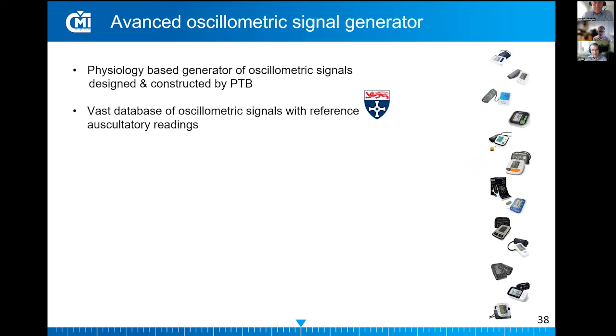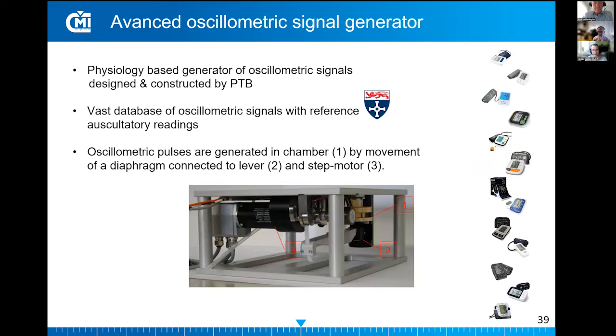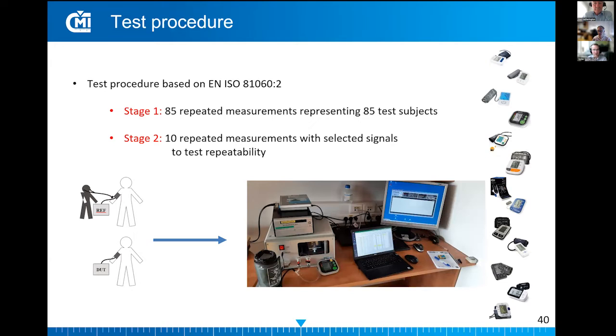As I mentioned, the device that we used for testing was our advanced oscillometric signal generator, which utilizes a vast database of oscillometric signals, with courtesy of Newcastle University. And these were used for the testing. Once again, this is how the device is constructed, what its key components are, and how we tested. Our test procedure consisted of two stages. The first consisted of 85 repeated measurements representing 85 test subjects, and the second was to test the repeatability of measurements with selected signals.